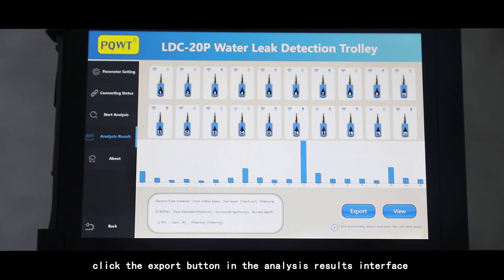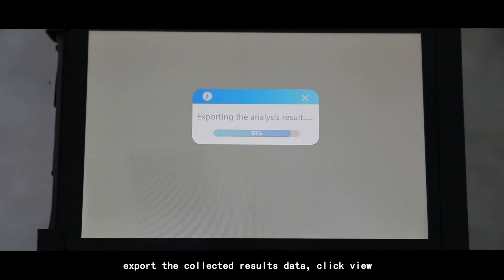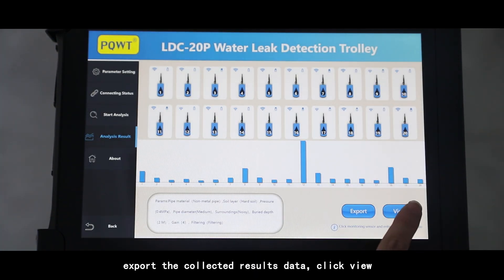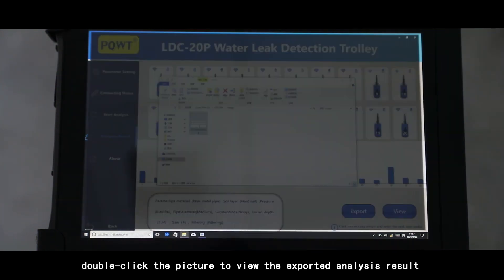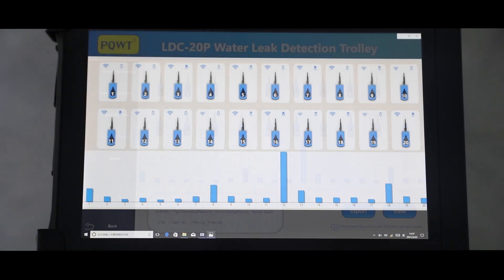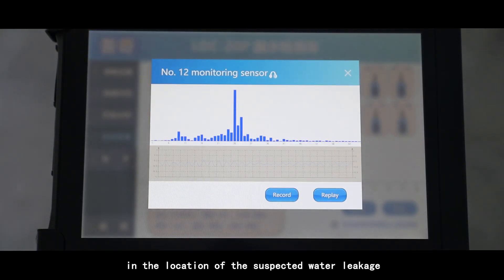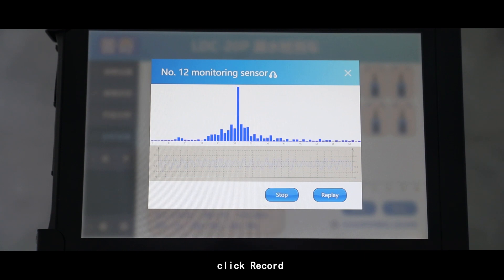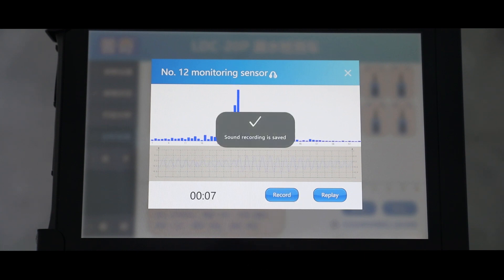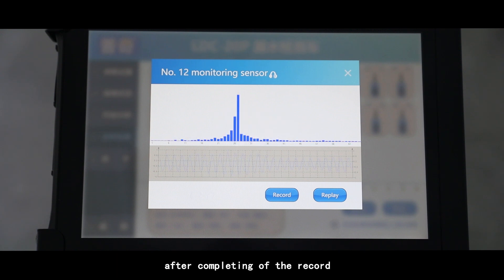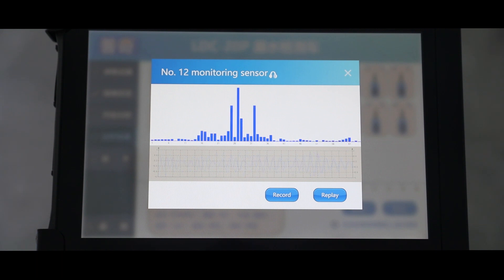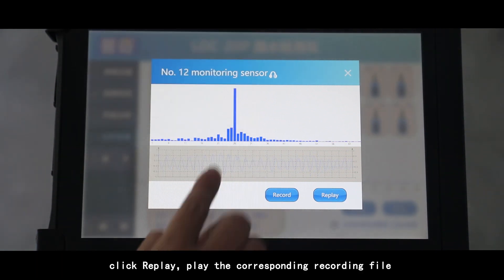Data export and view: Click the export button in the analysis results interface to export the collected results data. Click View and double-click the picture to view the exported analysis result. Click the icon of the monitoring sensor in the location of the suspected water leakage, click Record, then click Stop after completing the record. The sound of the water leakage is automatically saved. Click Replay to play the corresponding recording file.